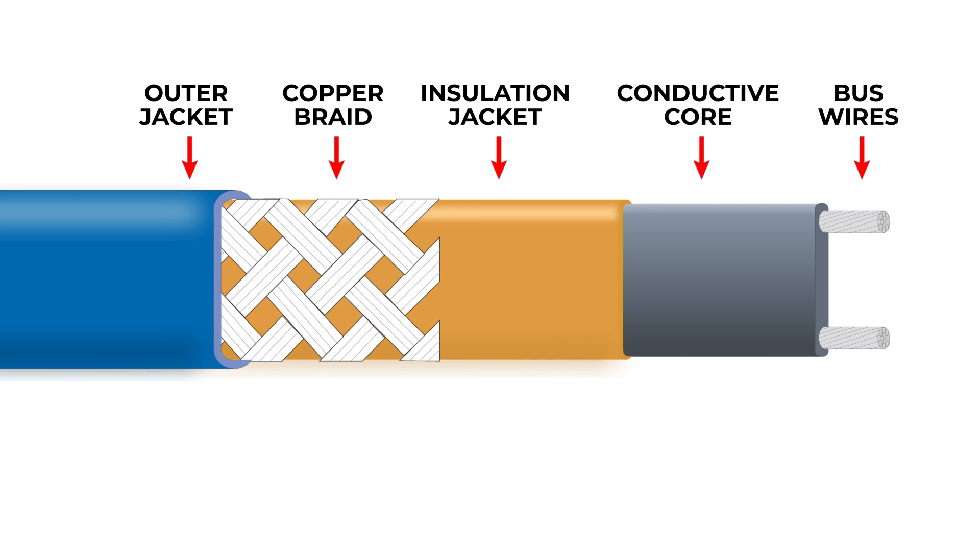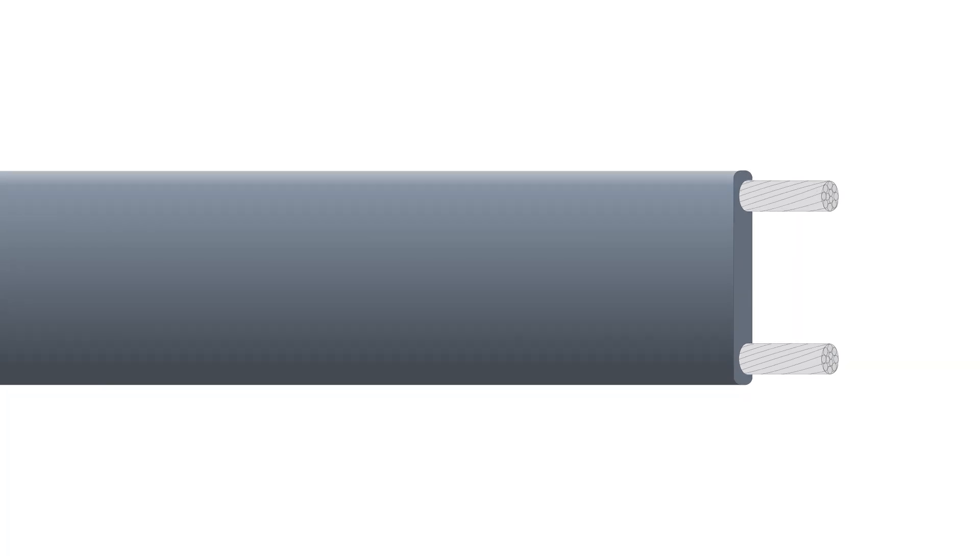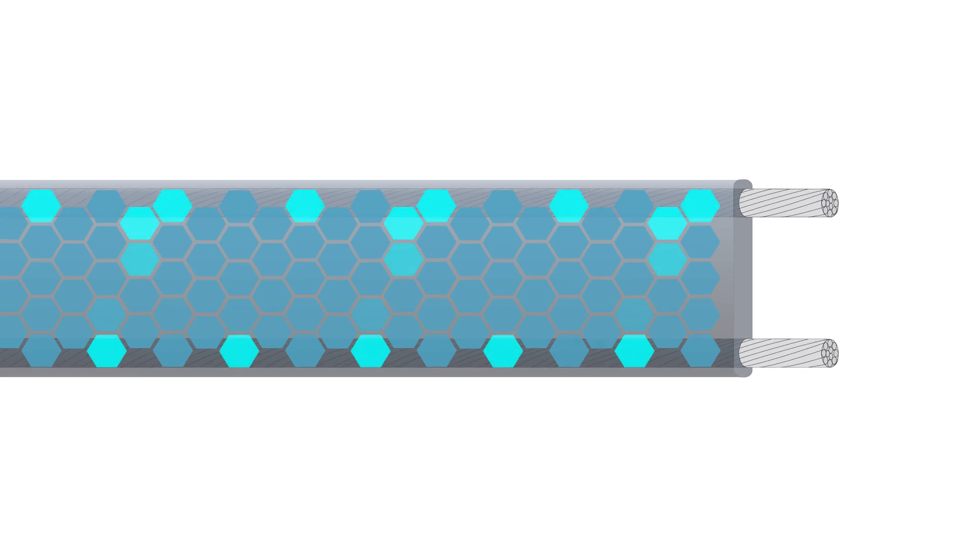Here's how it works: the core is made of a special plastic infused with millions of microscopic conductive electrical cells or pathways. In lower temperatures, the core contracts causing more of the conductive cells to come in contact with one another, completing the circuit between the two bus wires.